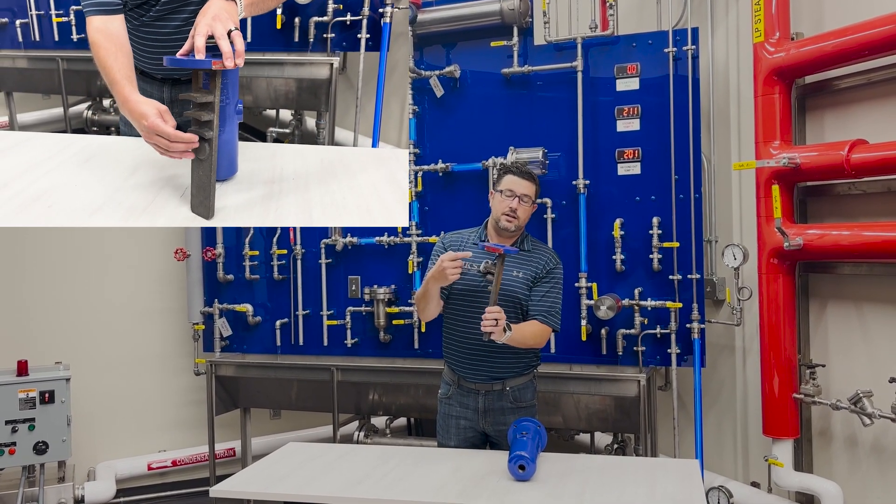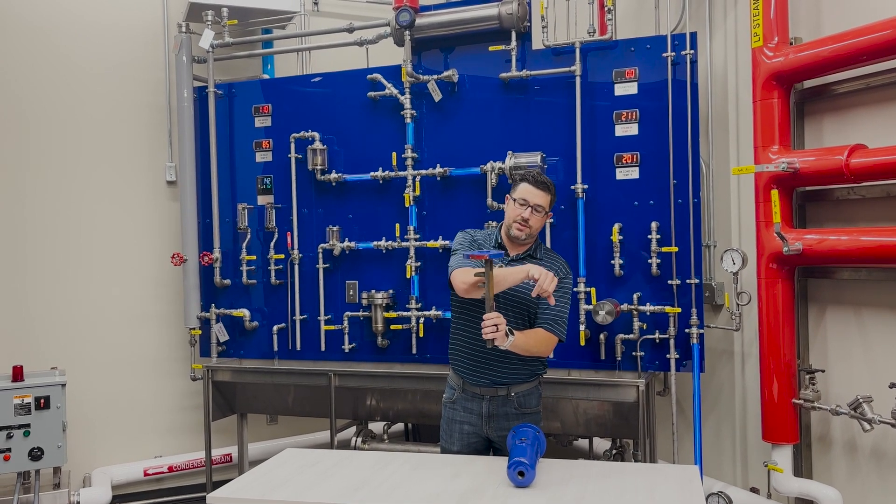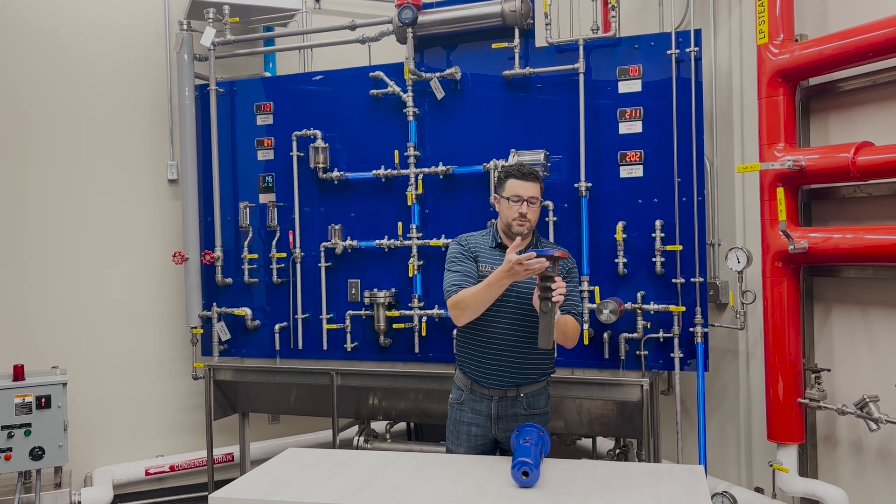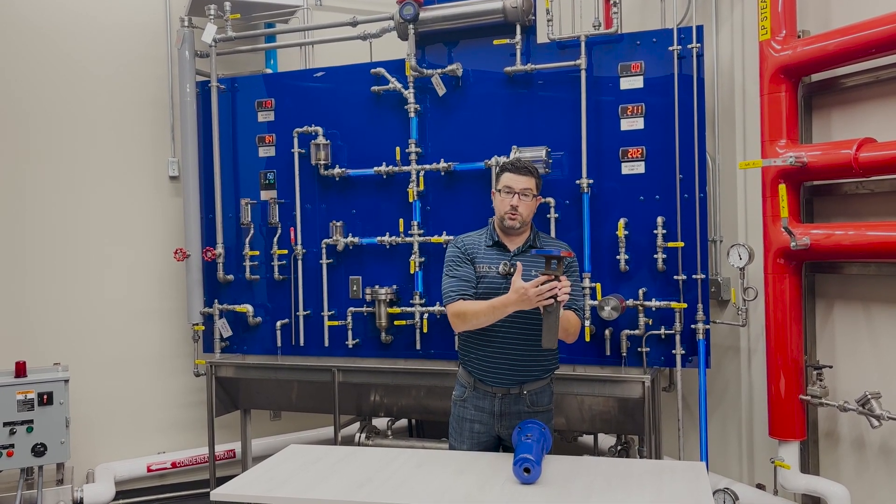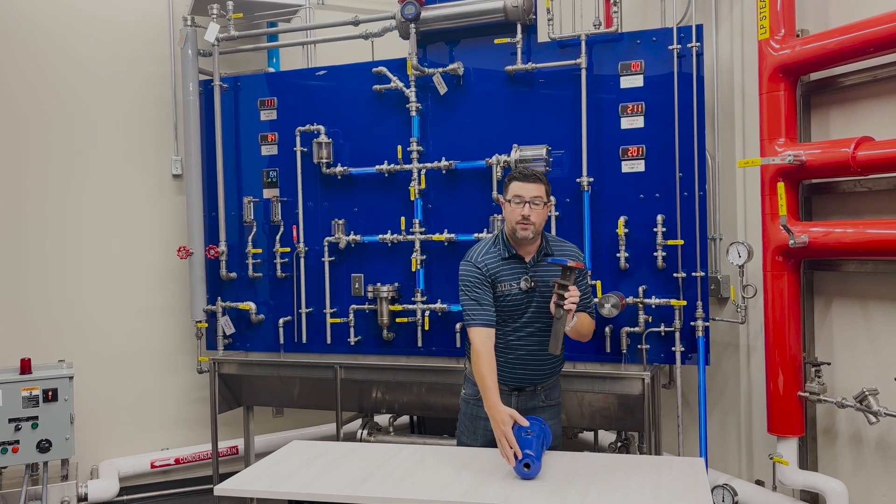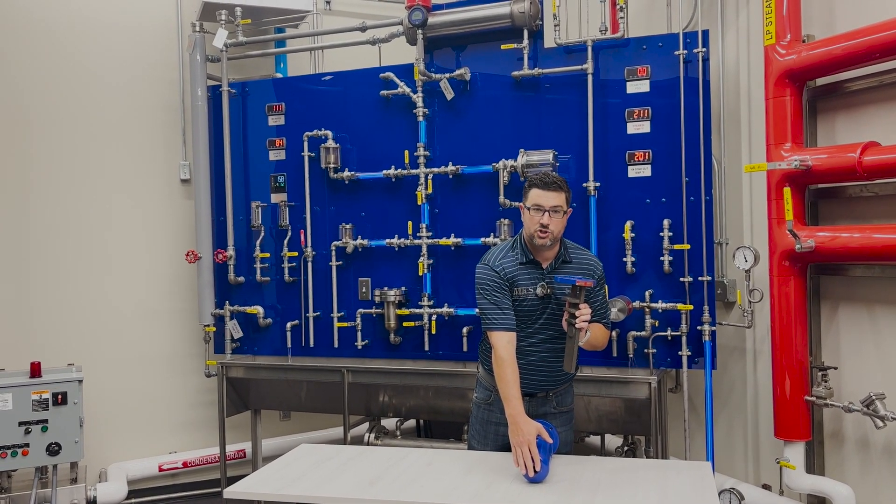So you've got clean, dry steam as a gas coming up and around the top. And all the entrained moisture is being forced by the baffles to flow down via gravity and come out the drain, which is piped out of the bottom of your separator.